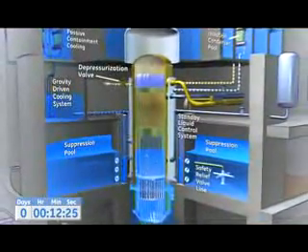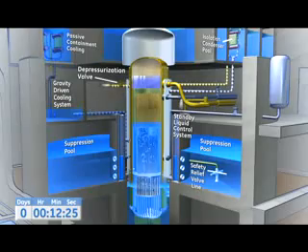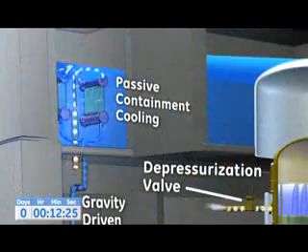A passive natural circulation cooling cycle then begins. As steam bubbles from the core drift to the surface, the steam then flows from the containment to low pressure heat exchangers in the PCC pool that condense the steam into water.